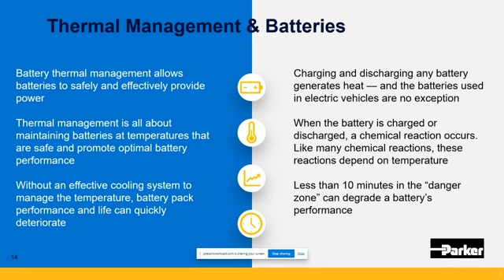increased temperatures. Low temperatures typically heavily reduce the power and energy capacity of the battery and increase its internal impedance. High temperatures increase the reaction rate, which results in the delivery of higher power and improved capacity, but at the same time leads to an even higher temperature and an increase in thermal load. Moreover, an additional problem caused by high temperature may be capacity fading because of electrolyte decomposition and non-uniformity of the passivation layer.